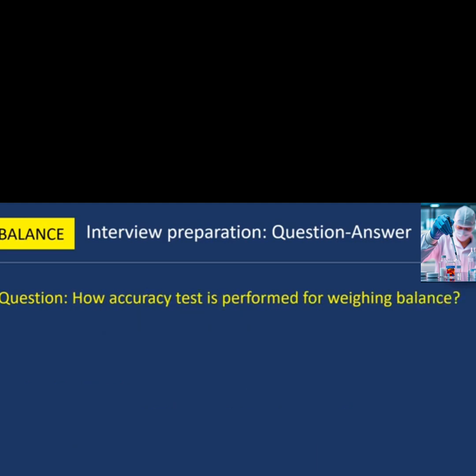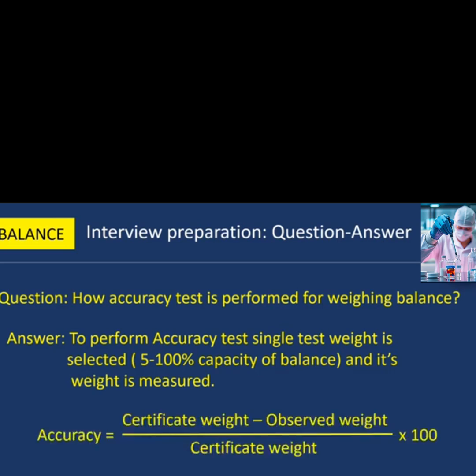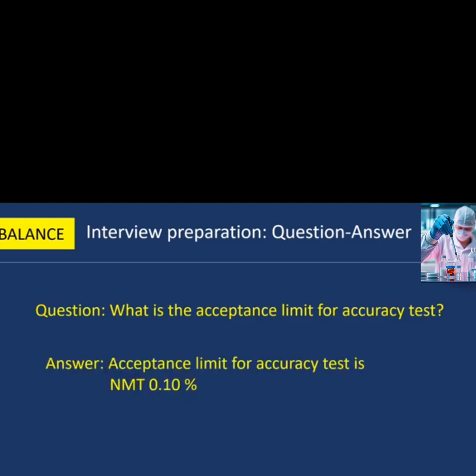Next question: how is the accuracy test performed for a weighing balance? To perform the accuracy test, a single test weight is selected between 5 to 100% of the balance capacity and its weight is measured. The formula is: Accuracy = (Certificate Weight − Observed Weight) ÷ Certificate Weight × 100. The acceptance limit for the accuracy test is not more than 0.10%.